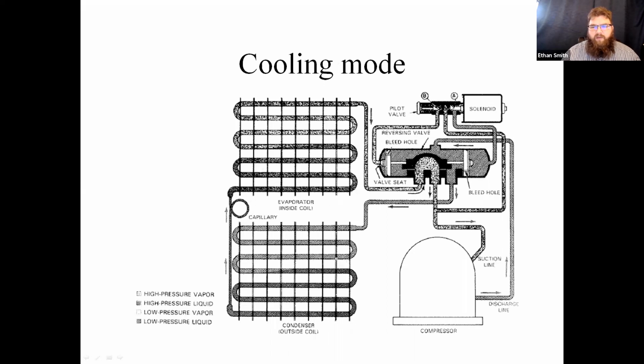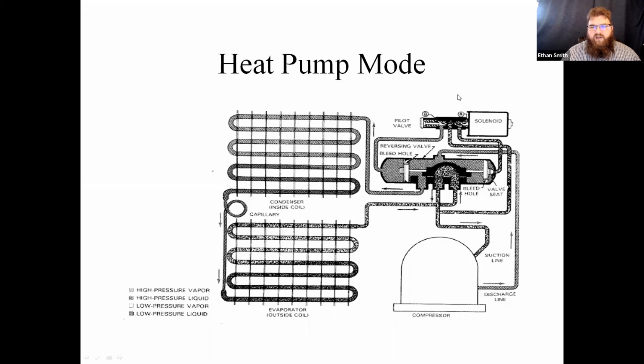Okay, that's going to pump high pressure gas into one side of this. It's going to hit that seal and push on that valve, and the suction side is going to actually suck the other side of the valve over to the other side of the valve body through the suction line as well. So it's a push-pull motion to move this. When we want to switch modes, we take that clamshell from here and we move it over to here. Okay, so now the clamshell is over here. We're putting high pressure gas into the other side of the pilot valve, and that pushes that valve armature and assembly inside the valve body over, moving our clamshell over.